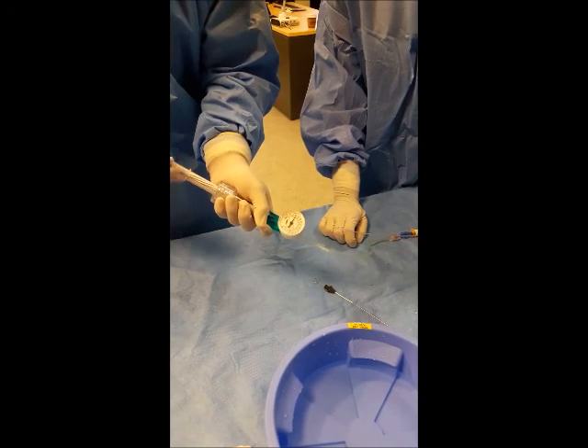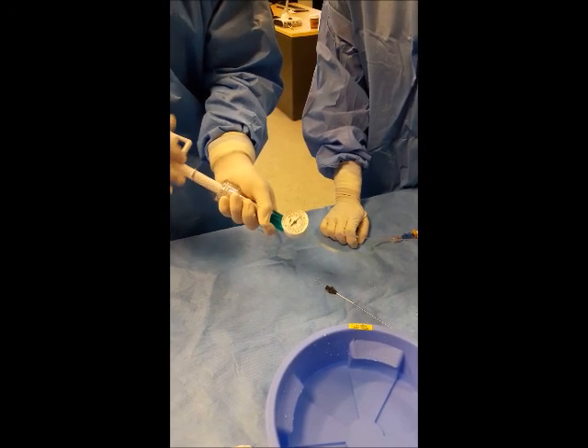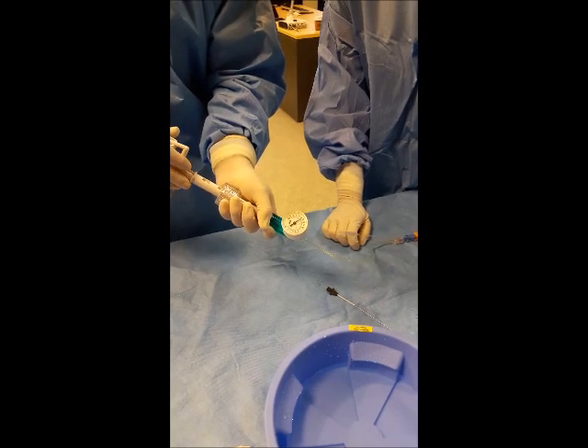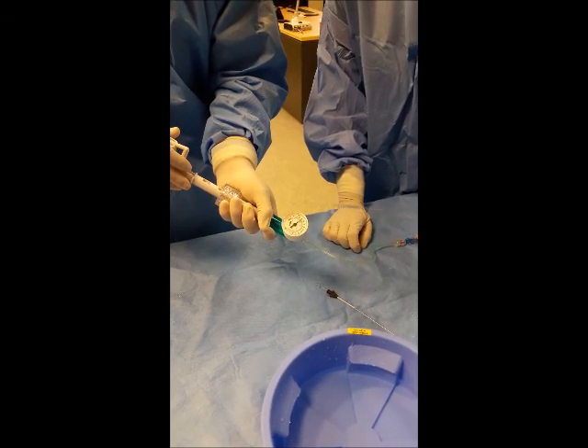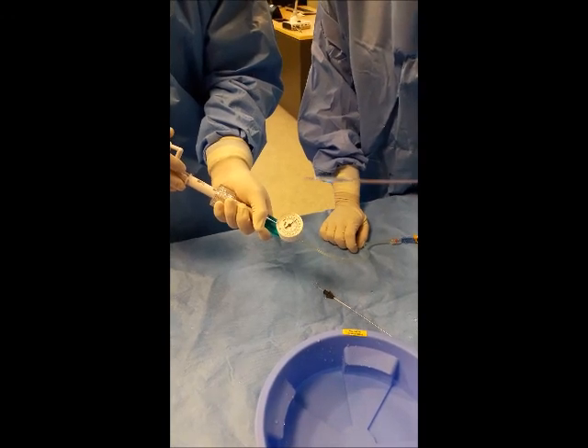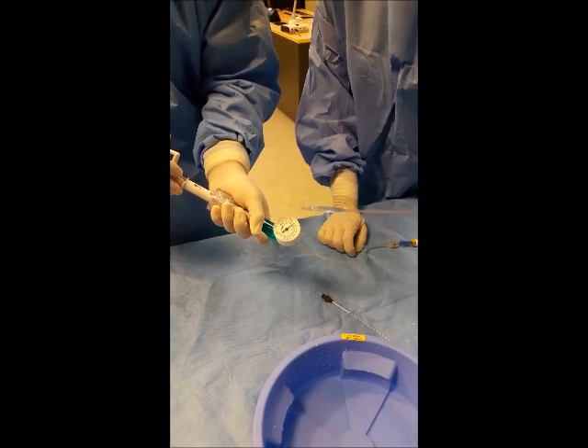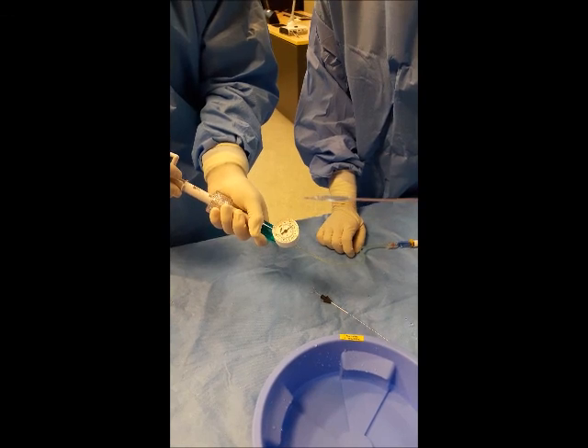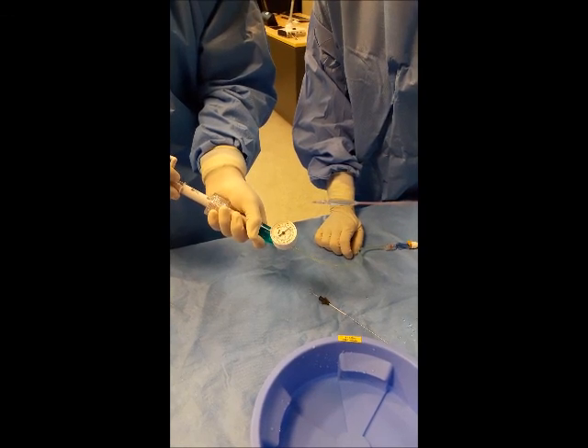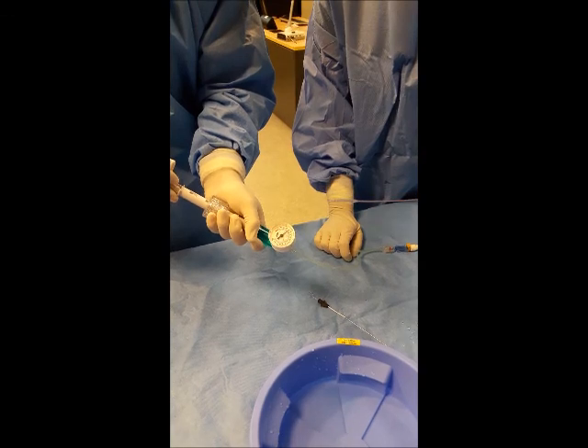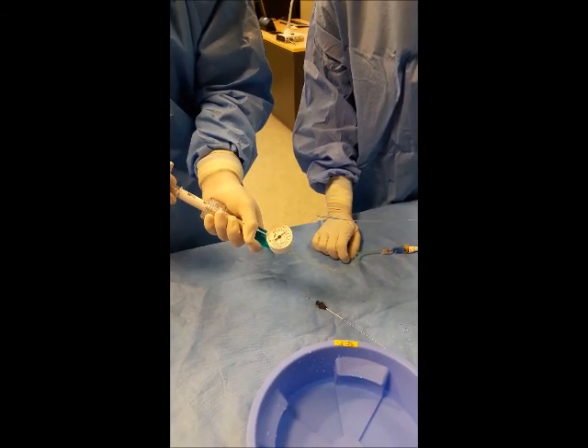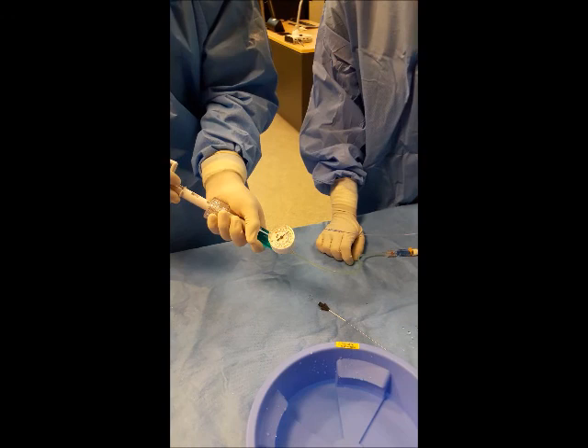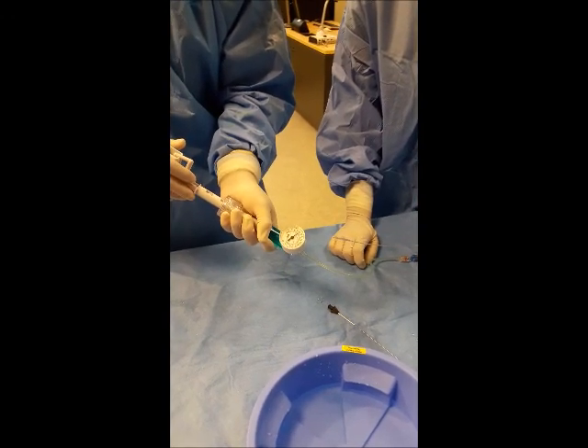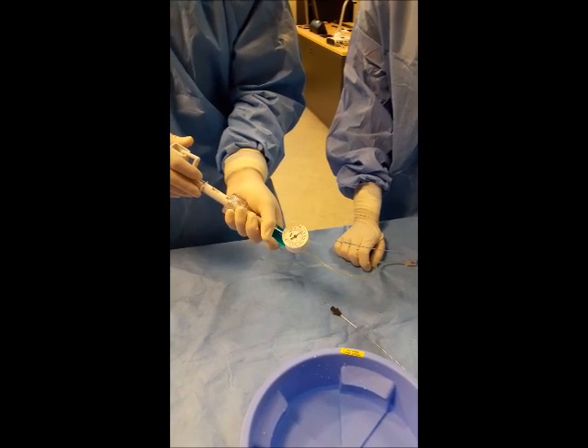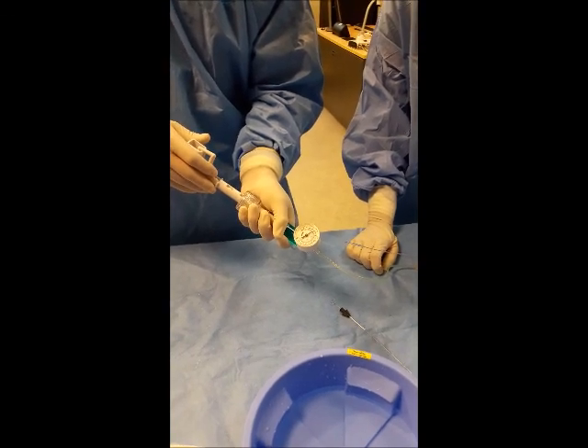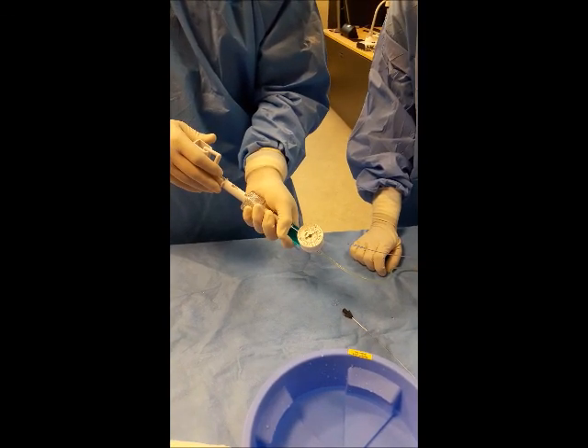If you have a scoring balloon, you must go up slowly to nominal at about 2 seconds per atmosphere, as well as come down slowly from nominal. While going up on a balloon inflation, always check placement, your waveform, atmosphere on the indeflator, heart rate, and blood pressure. When the physician is ready, he will ask you to come down. Release the pressure first by turning the handle a few times, then pull negative to decompress the balloon. Once the balloon or stent is out of the catheter, disconnect the indeflator, remove all air, and leave it ready for the next inflation.